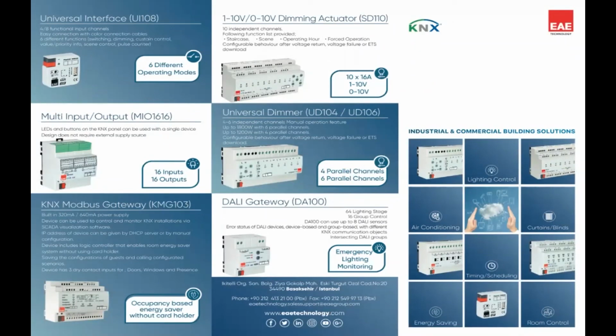With respect to dimmers, we have a universal dimmer, which is available in 4-channel and 6-channel, where each channel is around 300 watts. With respect to the analog dimmer, it's a 0 to 10 volt dimmer. The beauty is that it has a relay built into it, and it's a 10 channel relay. That's one of the most cost-effective products available in the market today. We have a brilliant DALI gateway, available in two versions. One is a normal gateway with 64 DALI addresses, and it does 16 groups. The other DALI gateway we have does 64 DALI addresses, and it does 64 groups.